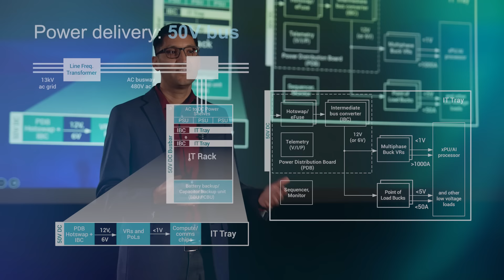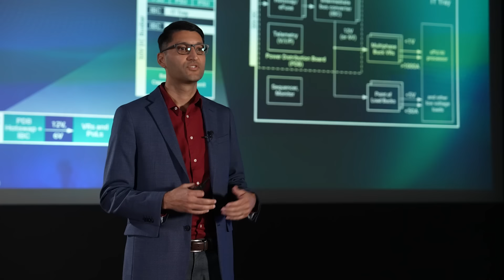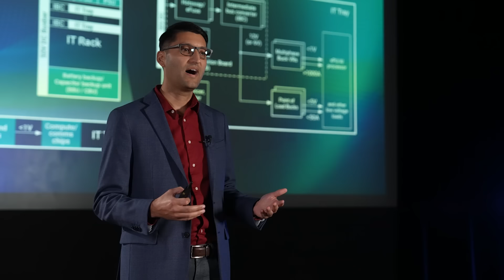This architecture is used when processor power is maybe 500 watts to a kilowatt kind of range, and you may have multiple processors included in each tray. So the PDBs in each tray are rated for many kilowatts, perhaps 5 to 10. The PSU shelves are rated for tens of kilowatts, and so when you add that all up, the total rack power might be over 100 kilowatts. But this approach tends to lose steam above around 200 kilowatts.